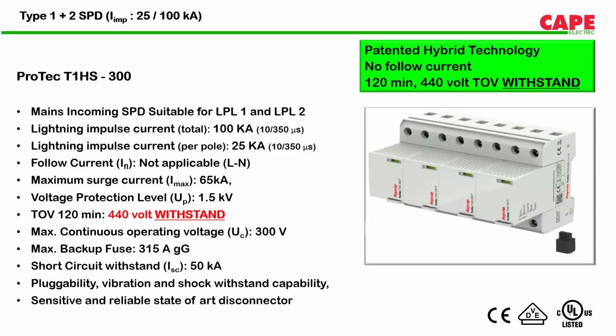Now, for example, in future, let's say after 4 or 5 years, due to some condition, R phase has failed. If SPDs are not pluggable, even failure of one phase means you'll have to change the complete SPD, the complete block. Here, in the pluggable SPDs, once R phase has failed, you can replace only the R phase. You don't need to replace the complete SPDs.